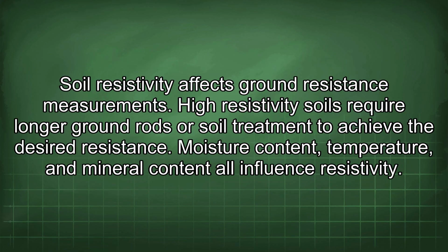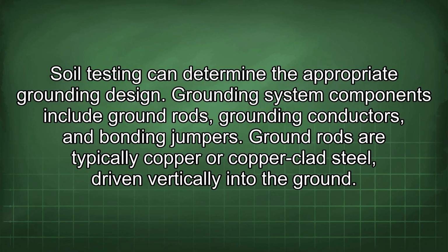Soil resistivity affects ground resistance measurements. High resistivity soils require longer ground rods or soil treatment to achieve the desired resistance. Moisture content, temperature, and mineral content all influence resistivity. Soil testing can determine the appropriate grounding design.